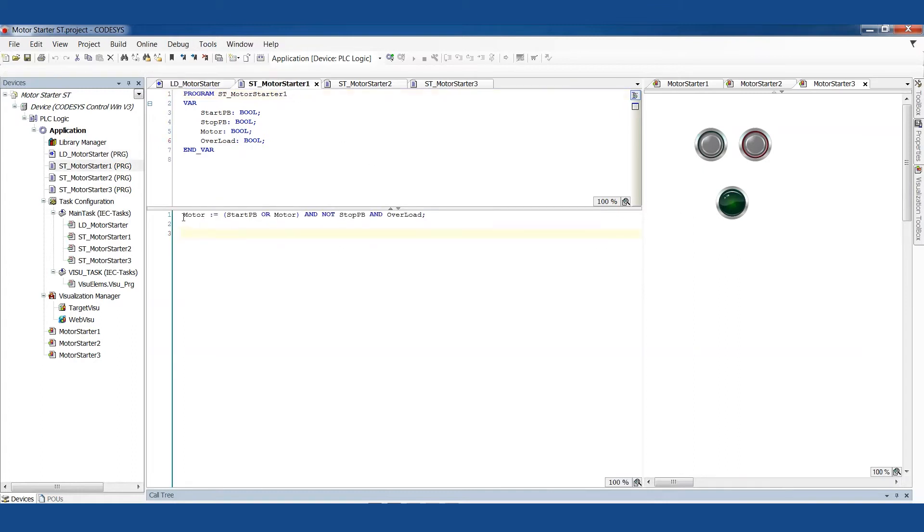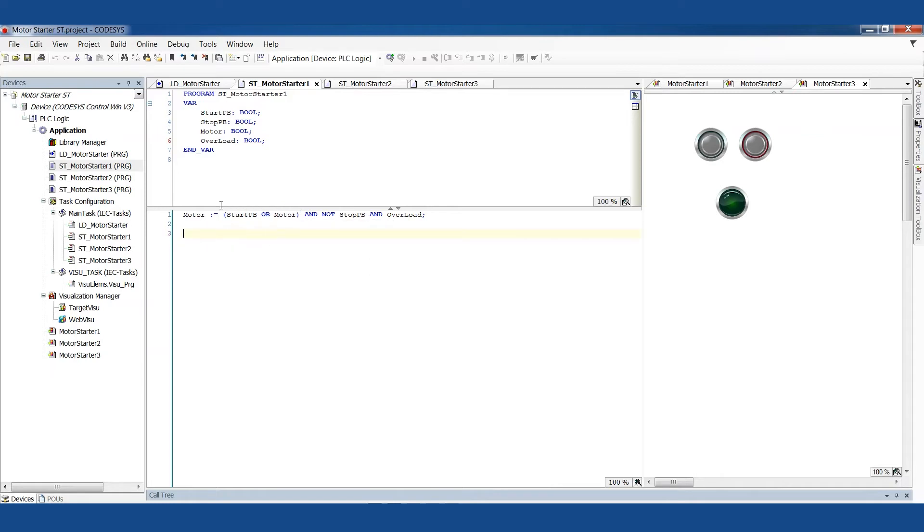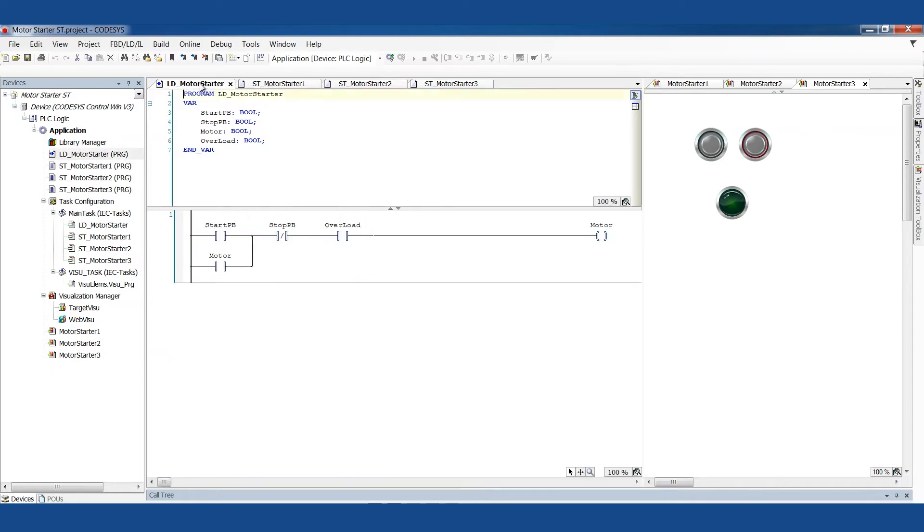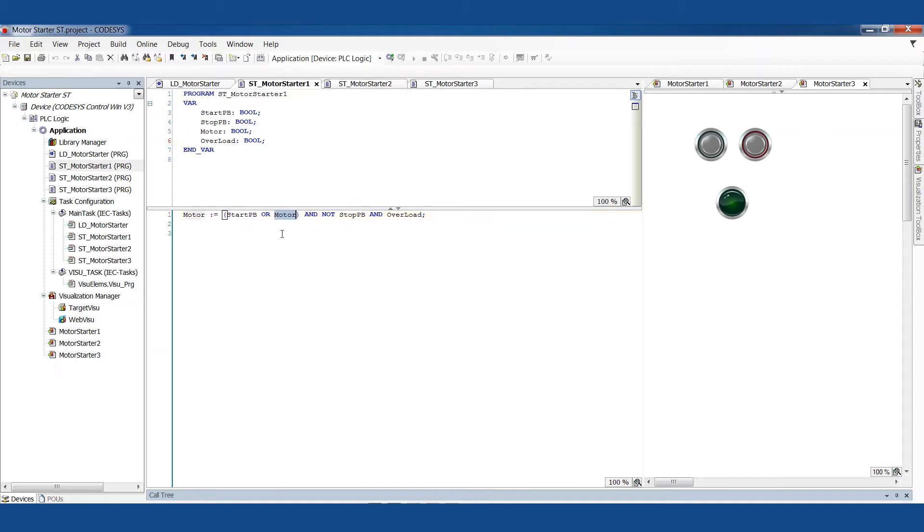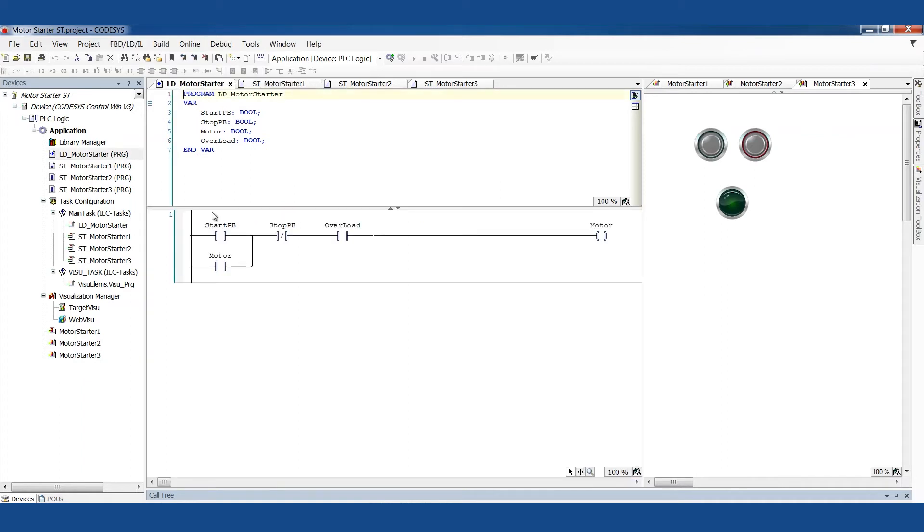So if we look at that in the structured text format, first of all you'll notice I've got parentheses around the start condition and the latch condition. And the reason I do that is because when we've got two things in parallel like this, because of the order of operations we have to tell the system that this needs to be assessed to be true or false before we continue the logic.